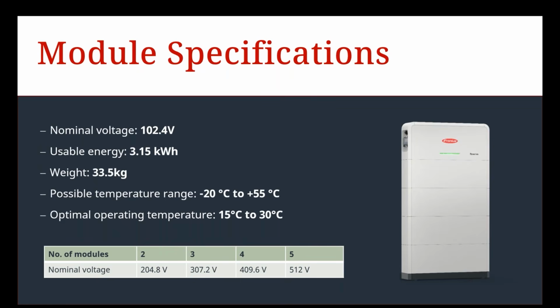The weight is around 33.5 kilogram. The Reserva itself has nice handles to actually stack the batteries on top of each other safely as a 1 or 2 person setup, depending on how many people you are on site. The possible temperature range: physically, the Reserva can do -20 to +55. Outside of that range, the battery will derate to 0 output in terms of charging and/or discharging. However, we do recommend the optimal operation temperature. For max performance and service life, we do recommend to stay roughly between 15 and 30 degrees Celsius. That'll increase the life and performance quite significantly. Therefore, we would always recommend an internal installation if it's possible, because as mentioned before, it is better in terms of the performance for the battery itself.